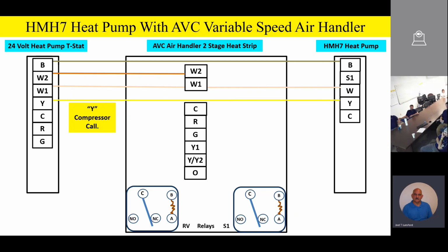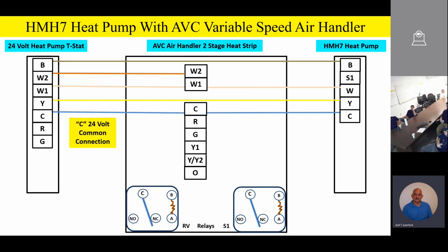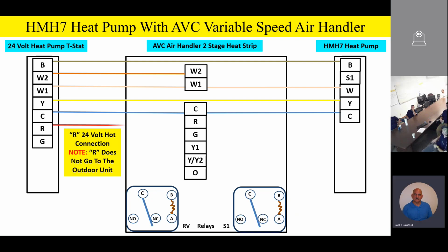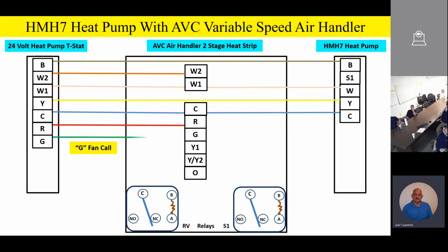Y signal goes outside, just like we had before, for our compressor call. C is our 24-volt common. That goes all the way through. R is 24-volt hot, and G is our fan call. Now, again, team, you'll notice that we've got 2 relays, and we're going to show you how that works here in just a second or two.